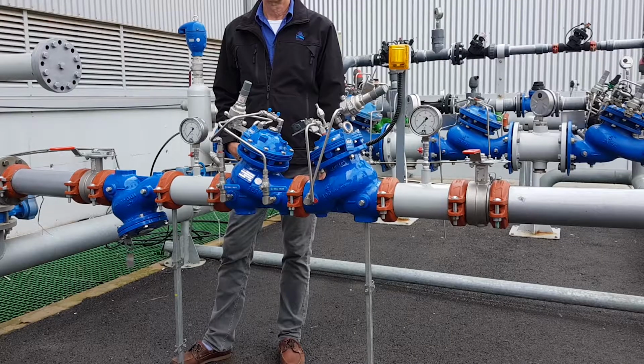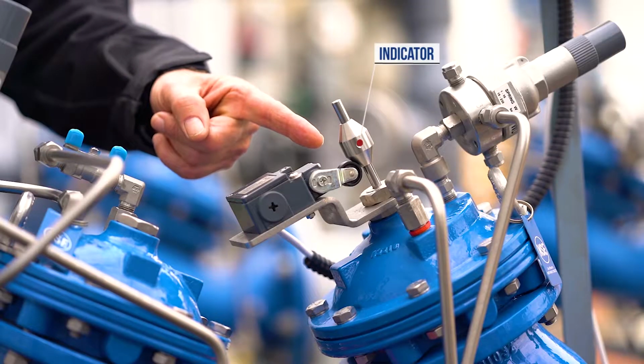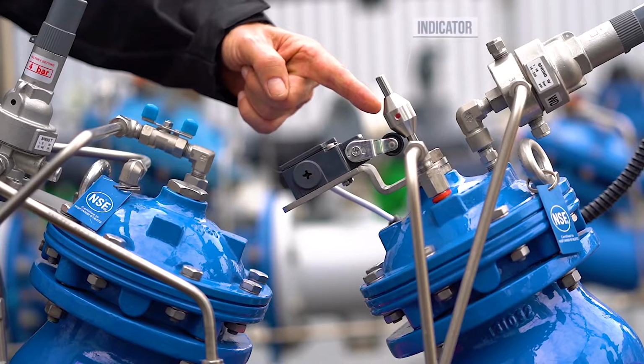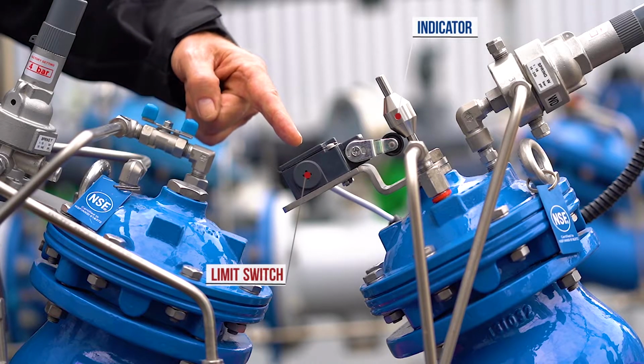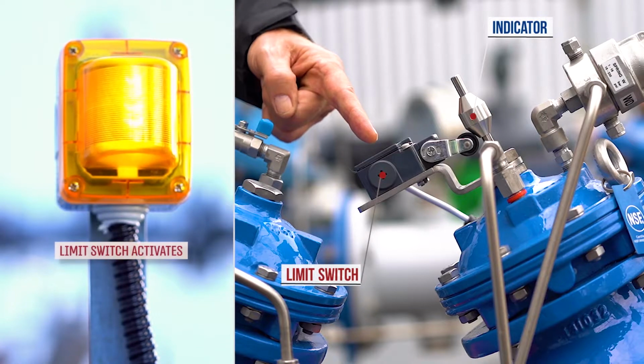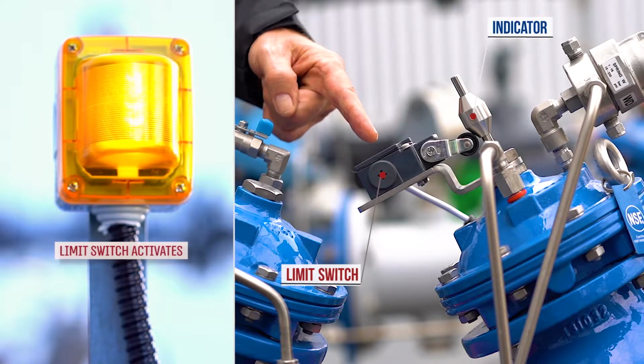When the shut-off valve closes, this indicator will move down. At this point, a limit switch will also be activated, which can send a signal to an alarm system or a control panel. This enables quick initiation of a corrective action by the maintenance team. Before we talk about commissioning procedures for this station, I'd like to present its major components.